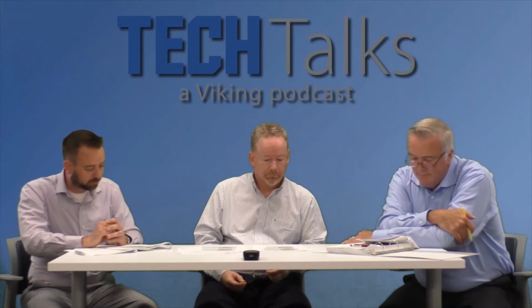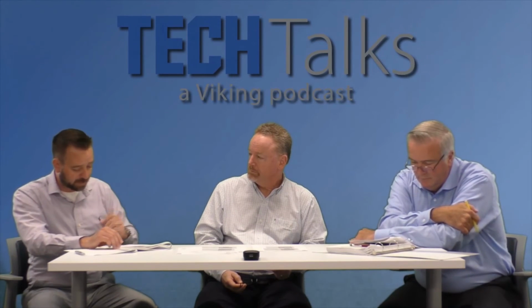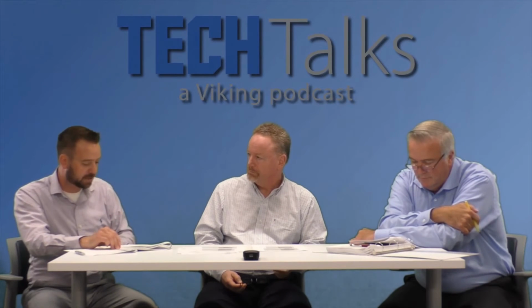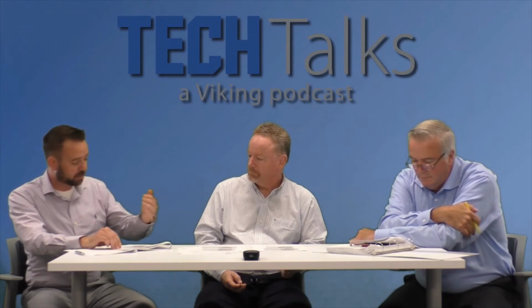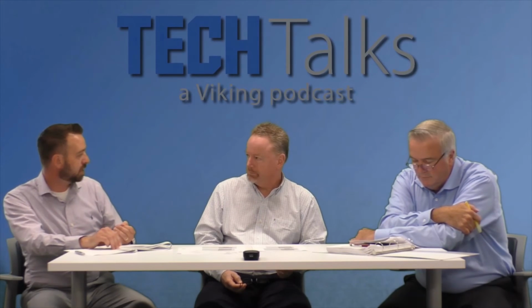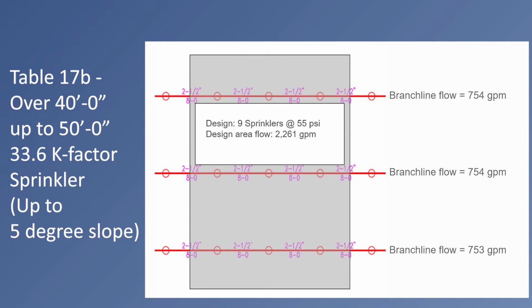Exactly, yep. And going to figure 4, now we start to see where, in this case, we're looking at the 33.6, and it's a 9 sprinkler design, so you have the 3x3x3, but it requires 55 PSI. So now we have a larger K factor than the 28K, as well as we're requiring 15 PSI more start pressure right there. Wow. So in this case, if you remember the previous with the K28, it was 1,611 for the calculated flow. Now with the 33.6K factor for the 9 sprinklers at 55 PSI, we're looking at a flow of 2,261 GPM.